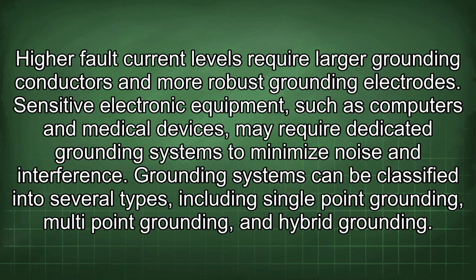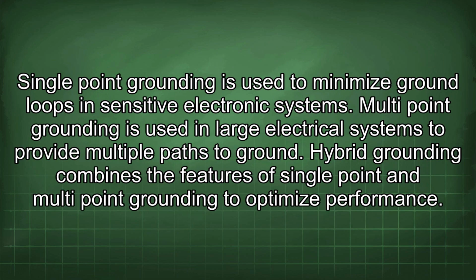Grounding systems can be classified into several types, including single-point grounding, multi-point grounding, and hybrid grounding. Single-point grounding is used to minimize ground loops in sensitive electronic systems. Multi-point grounding is used in large electrical systems to provide multiple paths to ground. Hybrid grounding combines the features of single-point and multi-point grounding to optimize performance.